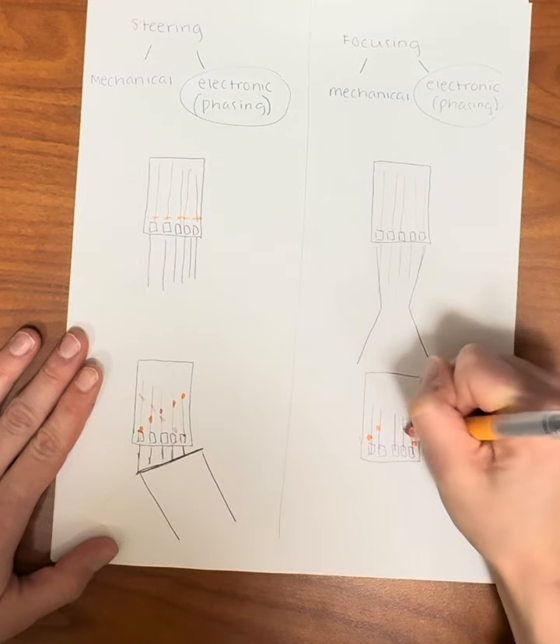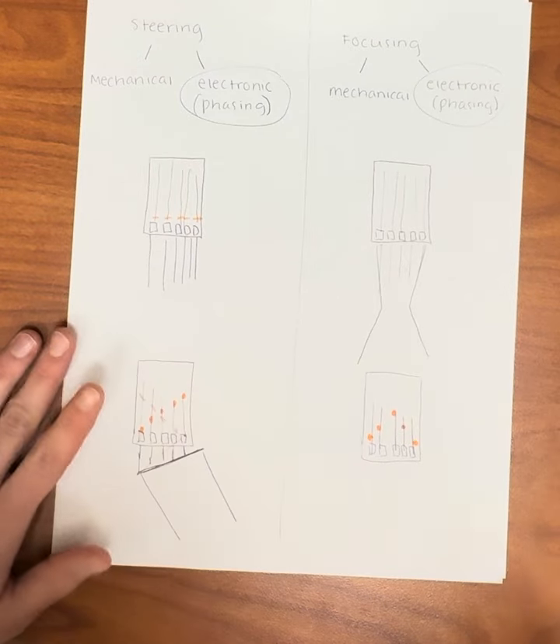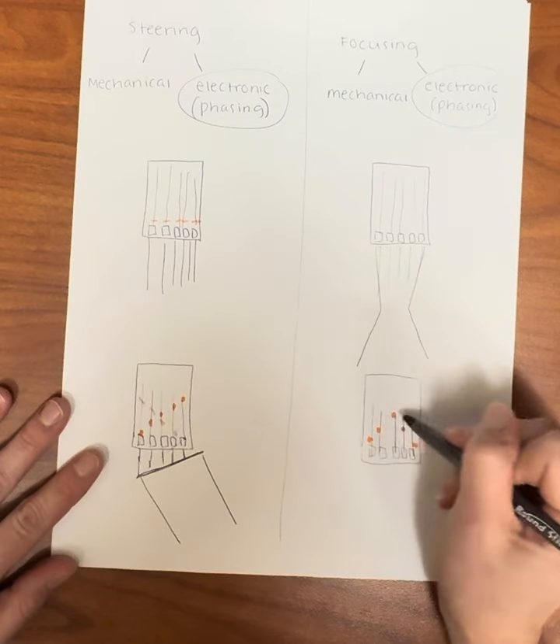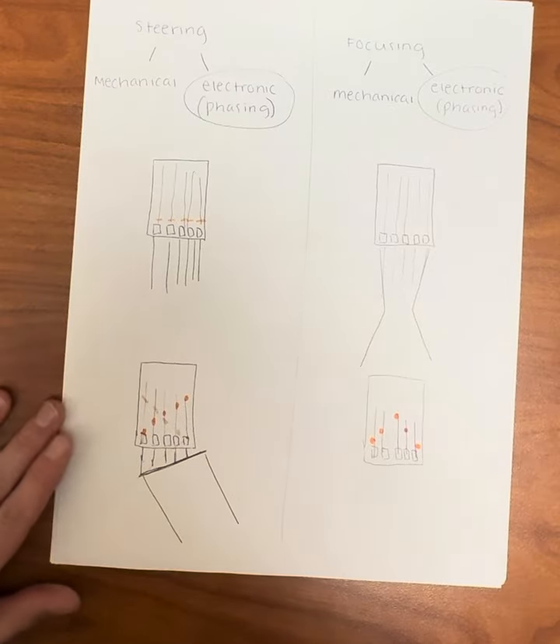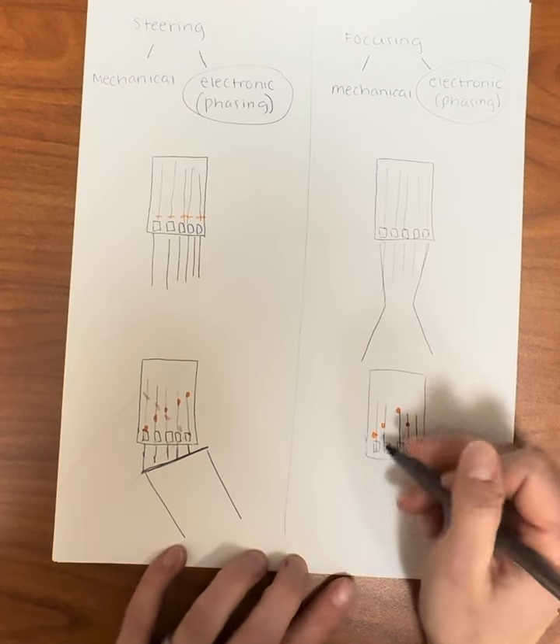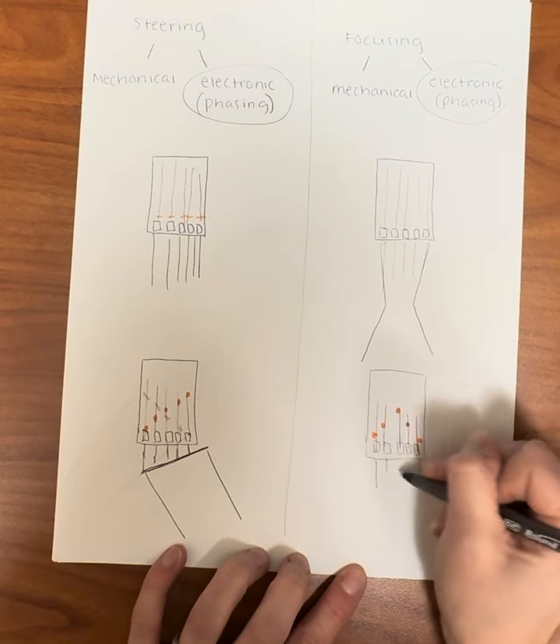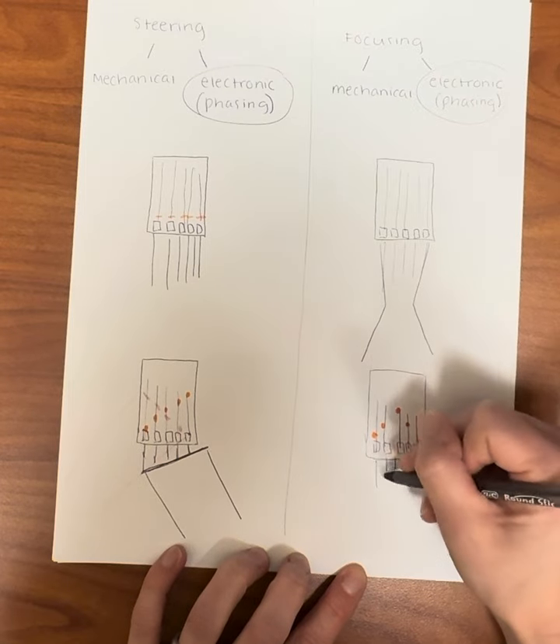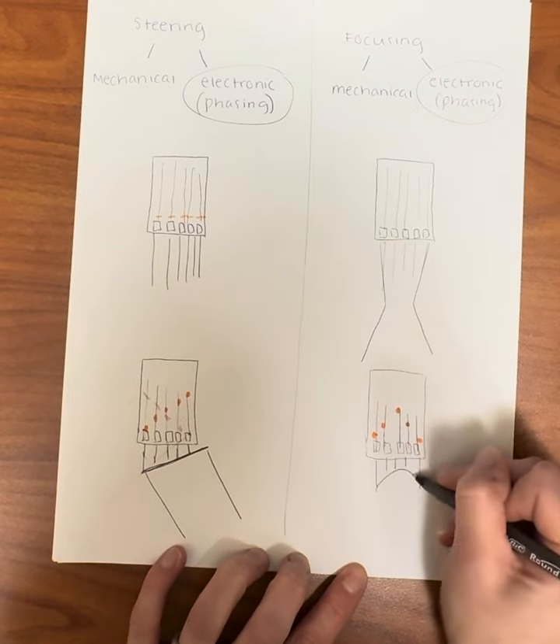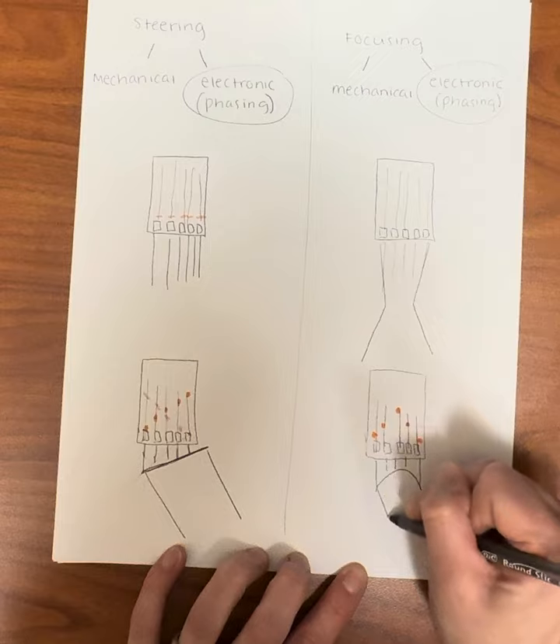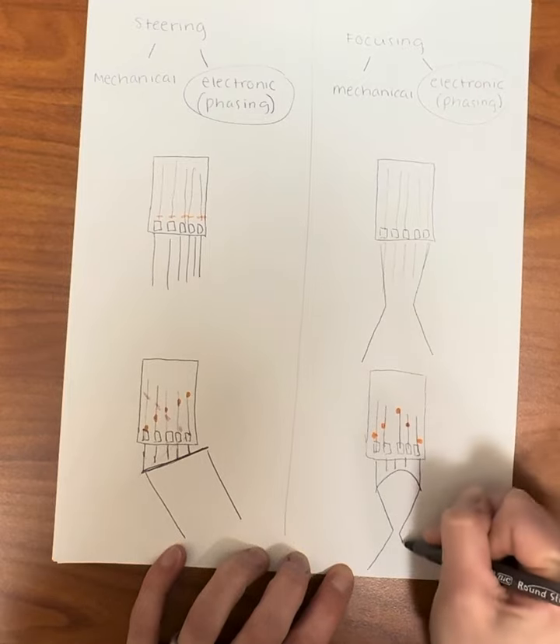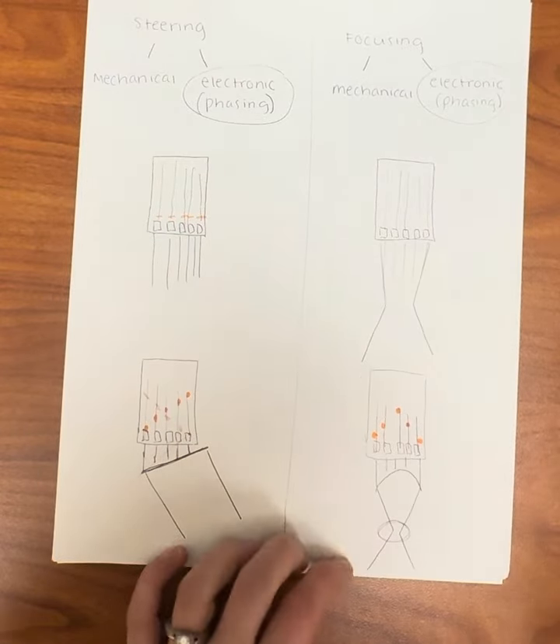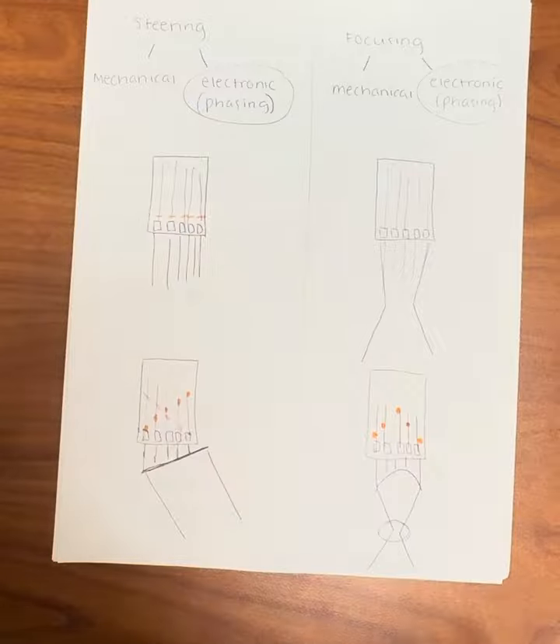But when we use a curved pattern, which means we're going to send our electrical signal on the outside, inner, all the way to our middle, and we have this curved pattern of sending our electrical signals, what happens is these go first, then these, then this one, and actually because of the way that they interact, they wind up creating a much narrower focus, and that is our focusing of our beam electronically.